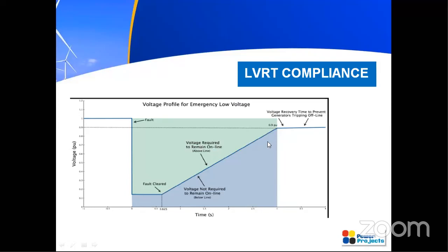So whenever the wind turbine is integrated with the grid, when your voltage dips from 0.9 per unit to 0.15 per unit, during this voltage dip your wind turbine should remain connected to your grid. Either the fault may be in one phase or in all the phases. Till this voltage drop clears, whether it is due to a fault or whatever, and till the voltage reaches this value, your grid-connected wind farm has to stay connected. That is the main point. That is the main requirement by the Indian Grid Code.